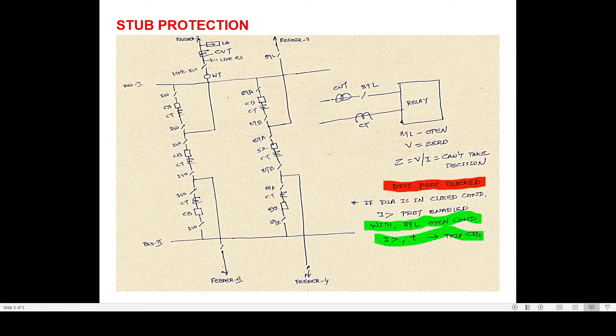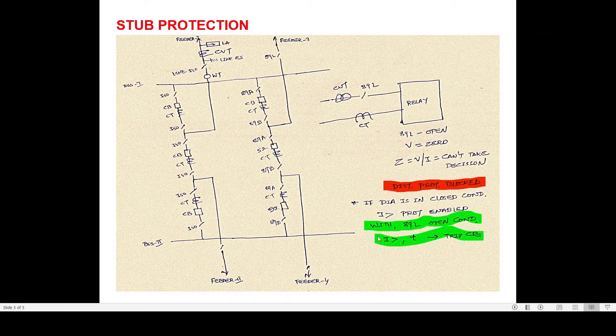So distance protection is blocked. If your bus section is closed — that means if these isolators and breakers are all closed — to protect this section you need a protection system. That protection system must be of overcurrent nature only, because you cannot employ distance protection now since your distance relay doesn't have any voltage input. The 89L open condition and I greater than the threshold — that is overcurrent protection — after a sufficient settable time delay, generally 100 milliseconds, it will issue a trip command.